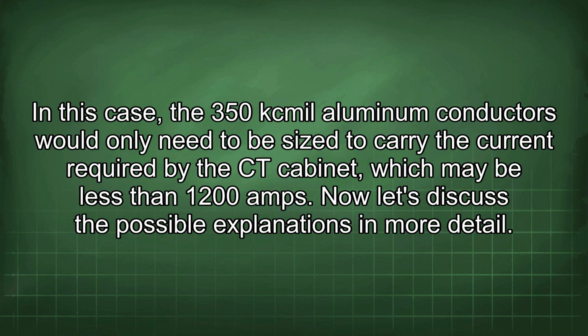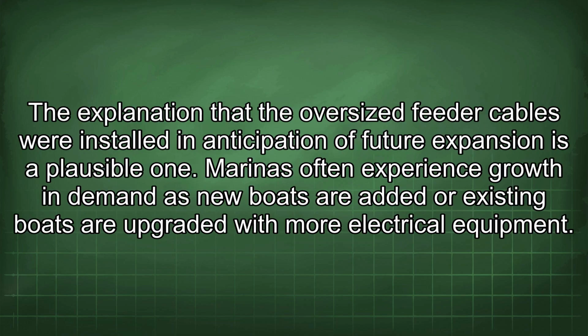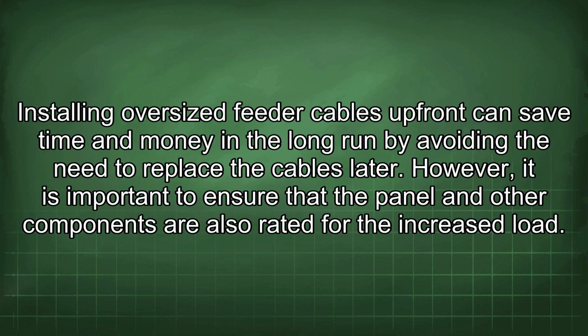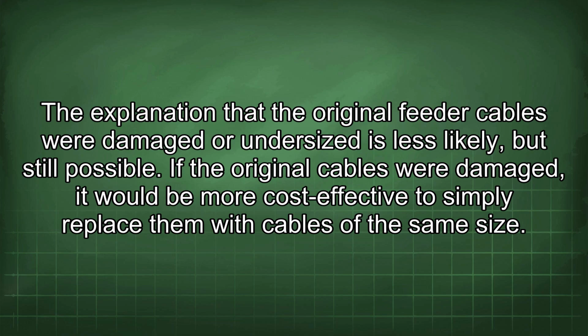Now let's discuss the possible explanations in more detail. The explanation that the oversized feeder cables were installed in anticipation of future expansion is a plausible one. Marinas often experience growth in demand as new boats are added or existing boats are upgraded with more electrical equipment. Installing oversized feeder cables upfront can save time and money in the long run by avoiding the need to replace the cables later. However, it is important to ensure that the panel and other components are also rated for the increased load.